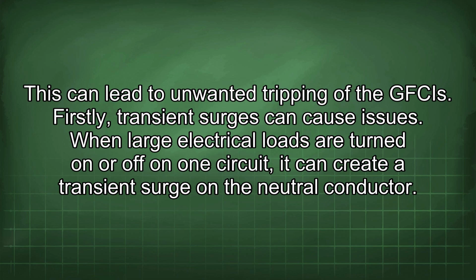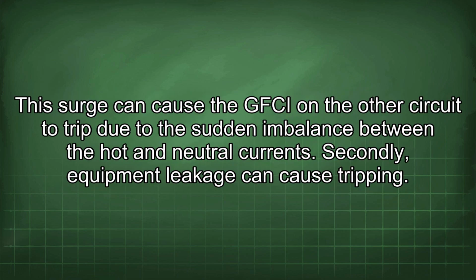Firstly, transient surges can cause issues. When large electrical loads are turned on or off on one circuit, it can create a transient surge on the neutral conductor. This surge can cause the GFCI on the other circuit to trip due to the sudden imbalance between the hot and neutral currents.